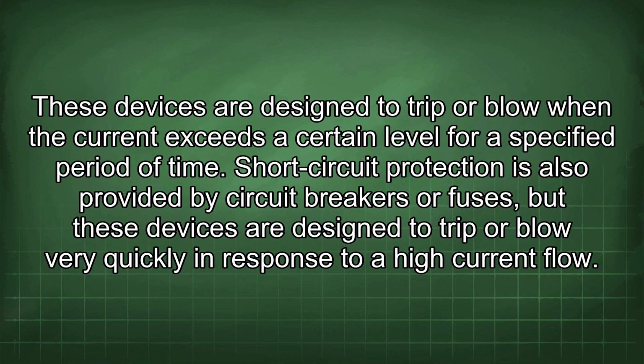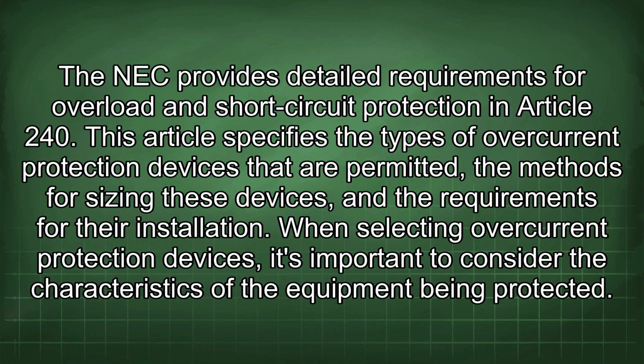Overload protection is typically provided by circuit breakers or fuses that are sized to protect the equipment from overheating. These devices are designed to trip or blow when the current exceeds a certain level for a specified period of time. Short-circuit protection is also provided by circuit breakers or fuses, but these devices are designed to trip or blow very quickly in response to a high current flow. The NEC provides detailed requirements for overload and short-circuit protection in Article 240.